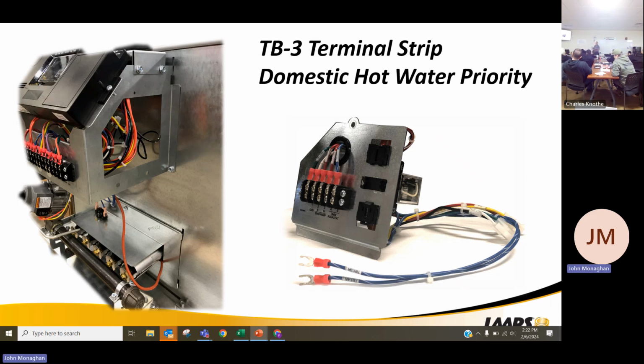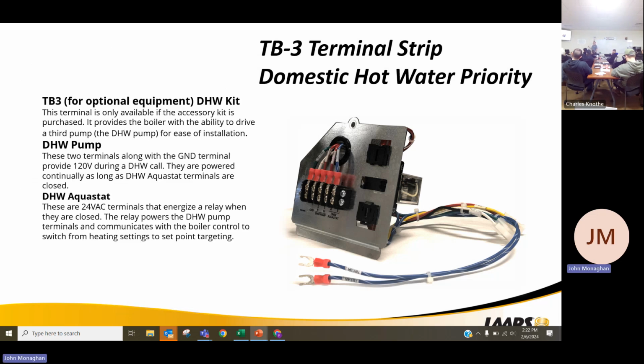Domestic hot water priority. If you wanted to do domestic hot water priority, this optional kit would give you the pump interlock. It would basically turn off the system pump and give the full boiler, all the BTUs, to your indirect. Again, there is no timer for this. It will continue to run. But it gives you domestic hot water priority. If you're going to be doing it through like a ZPC panel or an SR panel, if you're doing multiple zones, you can do your domestic hot water priority off of there as well.